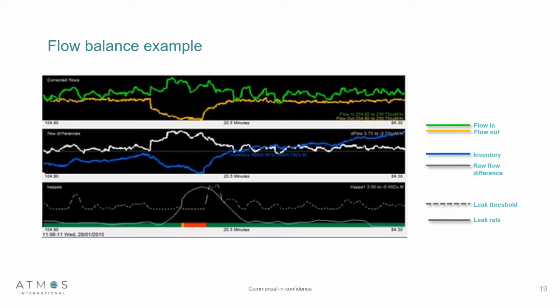Here is an example of our flow balance screen. As you can see here, this is a leak that's been generated, and you can see that there's a clear increase in flow at the inlet and a decrease in flow at the outlet. And our flow difference has picked that up.